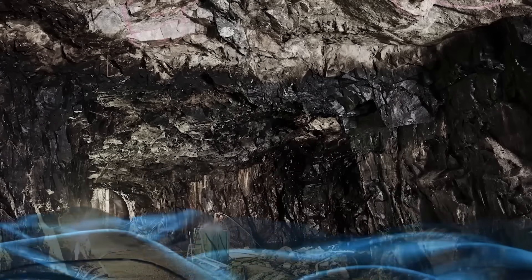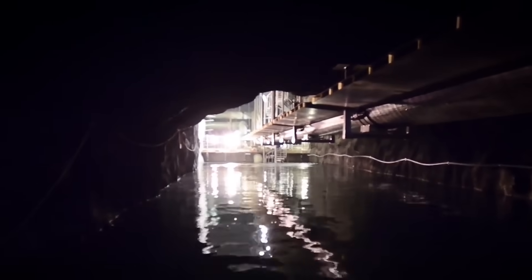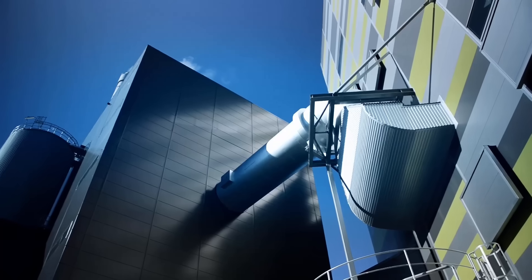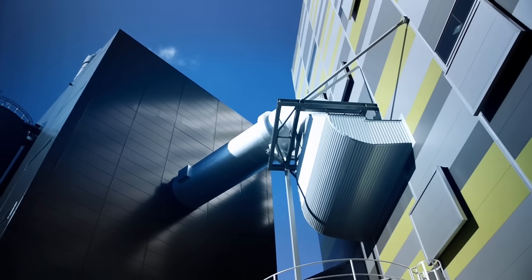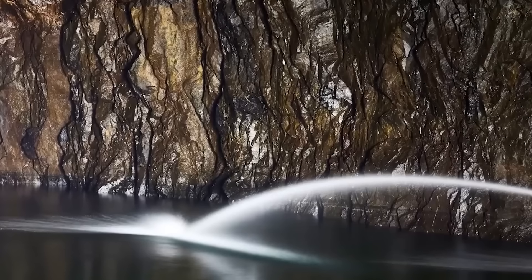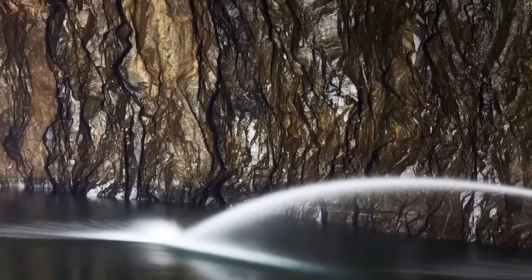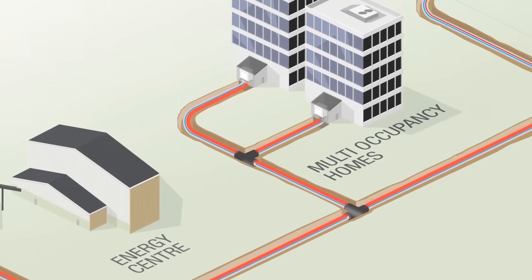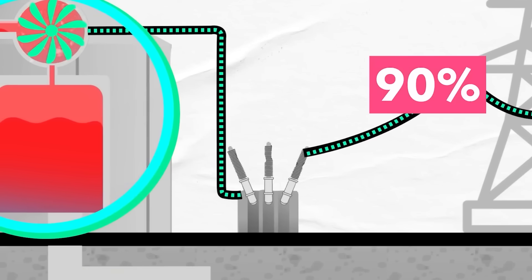This investment turned out to be as useful as one could imagine. Thanks to the underground storage of almost boiling water, the cogeneration plant in Västerås minimizes all the drawbacks mentioned earlier. A power plant can now easily operate in warm weather with minimal heat loss — the heat that's generated but not used doesn't disappear, but goes into heating the water in the caves beneath Västerås. When cold weather sets in, heat exchangers use the warmth from the underground water to heat the water circulating in the heating system.